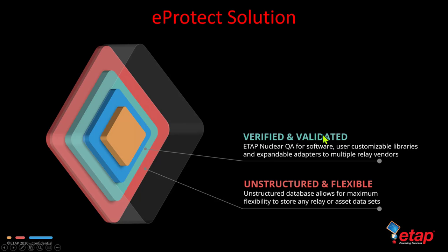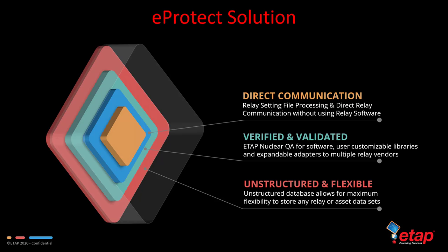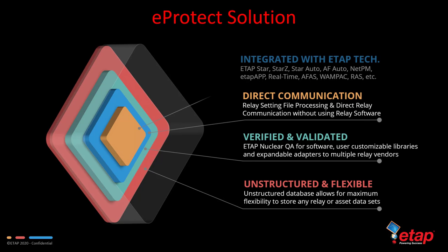eProtect also includes engineering libraries that are verified and validated under ETAP Nuclear QA. These libraries are of course user customizable, and we also offer expandable adapters that can communicate with other relay vendors that we may not have in our current library. The ability to have these expandable adapters gives us the capability to perform direct communication, which means we are able to read and write setting files and process them directly and in many cases without using the relay software. The intent is not to bypass the relay software, but to improve the efficiency of reading and writing the settings and not necessarily change all the other parameters that the relay vendor software offers.